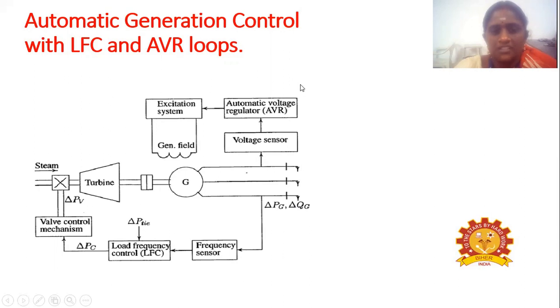This loop is called the excitation loop, and it is used to maintain the voltage. And this loop is called the load frequency control loop. It helps to maintain the constant frequency. So there are two loops: one is the load frequency control loop, and the other is the AVR, that is the automatic voltage control loop. The function of the AVR loop is to maintain constant voltage. The function of LFC is to maintain constant frequency. First we'll see the LFC loop.